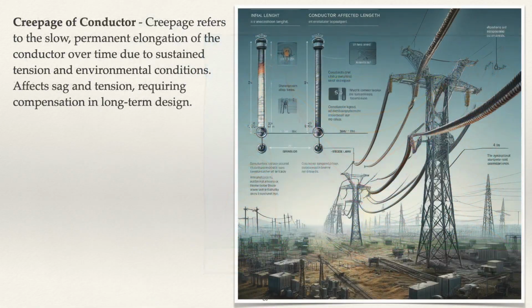Creepage of conductor. Creepage refers to the slow, permanent elongation of the conductor over time due to sustained tension and environmental conditions. Affects sag and tension, requiring compensation in long-term design.